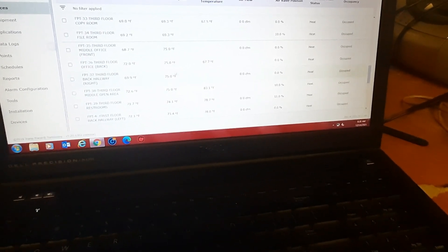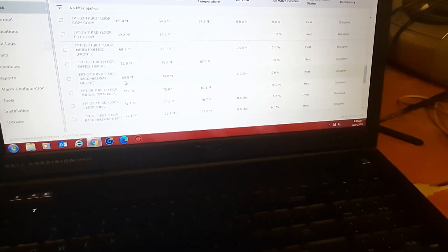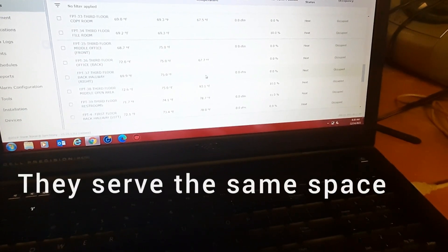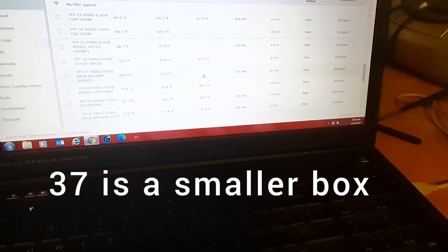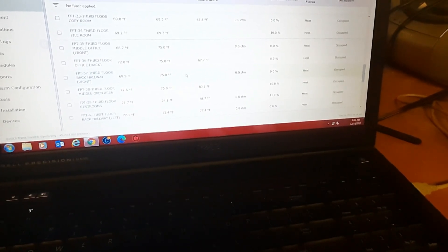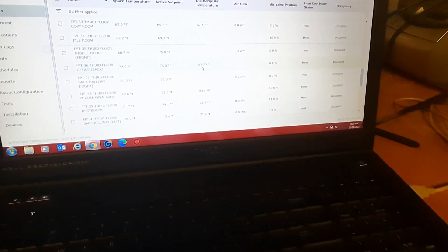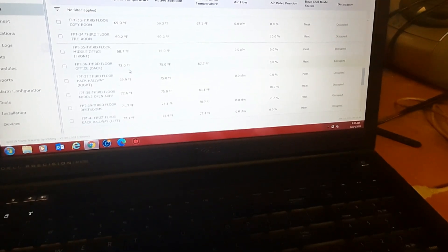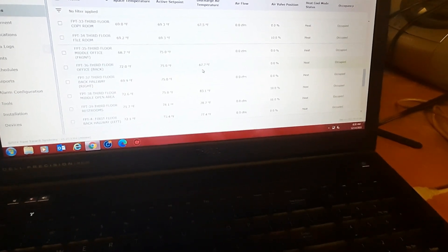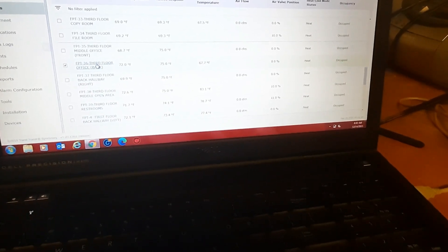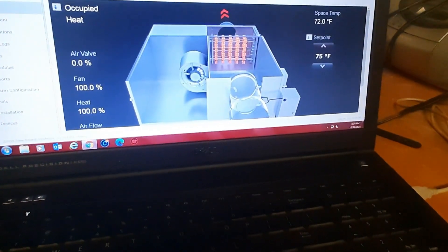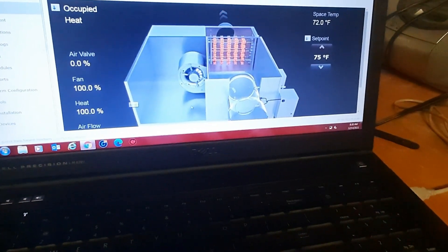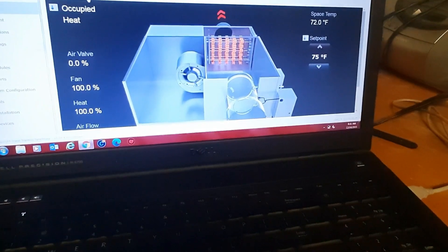And this is the one in question. So I've got some parts. This one is actually heating yesterday. As you can see, I've got no discharge temperature, that's because my discharge temperature probe has failed. And then this one you can see I'm putting out 67 degrees. It's going to be hard to heat that space. It's actually a whole lot warmer today because I was able to close the damper a little bit. So we can see our heat's at 100% and it shows my little graphic there where the heat is on.